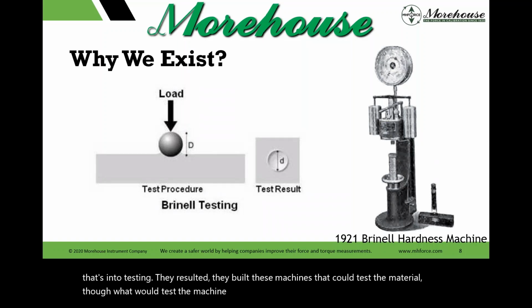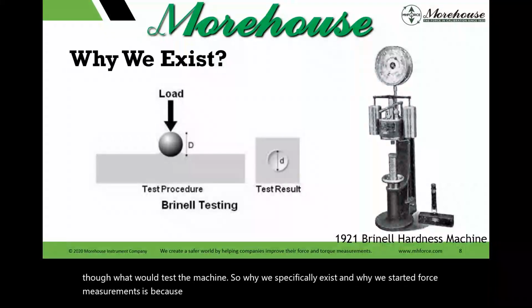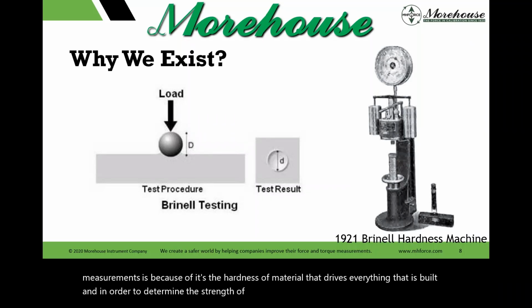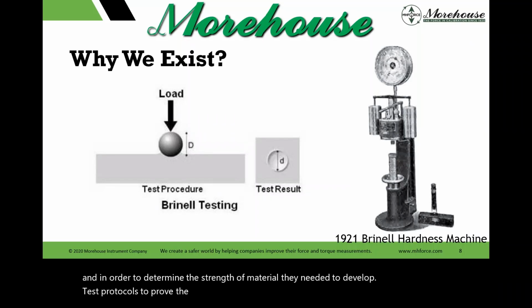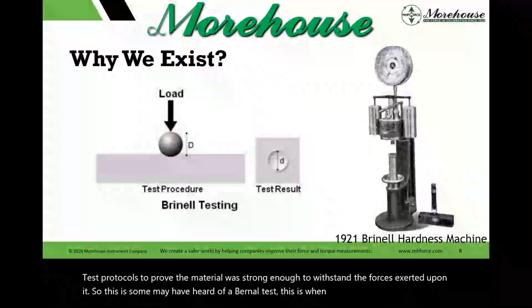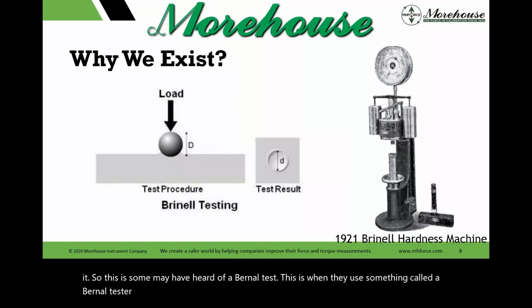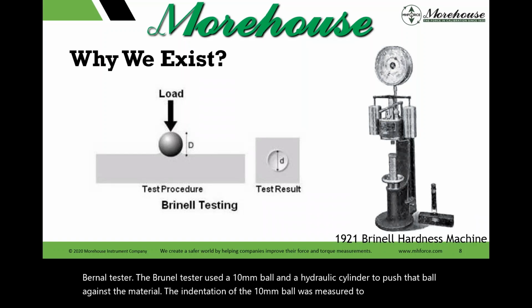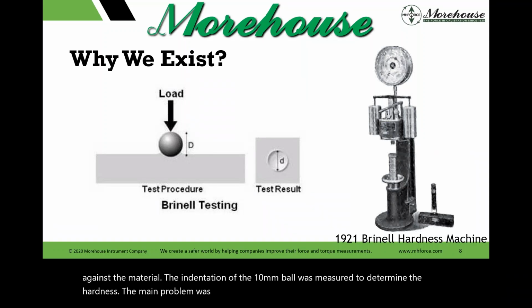So why we specifically exist, and why we started force measurements, is because the hardness of material drives everything that is built. In order to determine the strength of material, they needed to develop test protocols to prove the material was strong enough to withstand the forces exerted upon it. Some may have heard of a Brinell test. This is when they use something called a Brinell tester. The Brinell tester used a 10-millimeter ball and a hydraulic cylinder to push that ball against the material. The indentation of the 10-millimeter ball was measured to determine the hardness. The main problem was that the hydraulic cylinder used to generate forces was described as inaccurate at best.